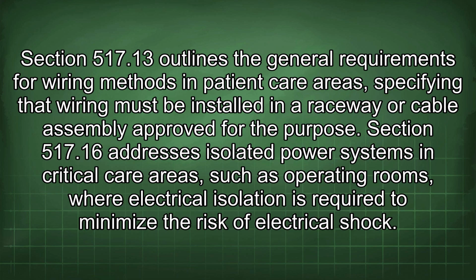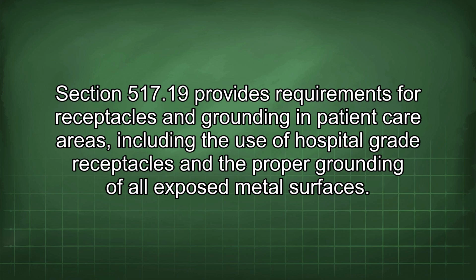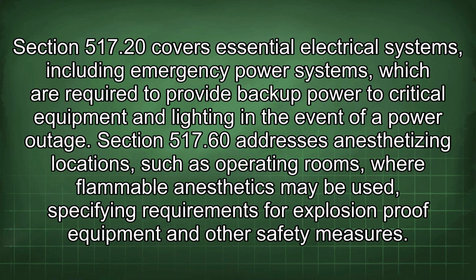Section 517.16 addresses isolated power systems in critical care areas, such as operating rooms, where electrical isolation is required to minimize the risk of electrical shock. Section 517.19 provides requirements for receptacles and grounding in patient care areas, including the use of hospital-grade receptacles and the proper grounding of all exposed metal surfaces. Section 517.20 covers essential electrical systems, including emergency power systems, which are required to provide backup power to critical equipment and lighting in the event of a power outage.